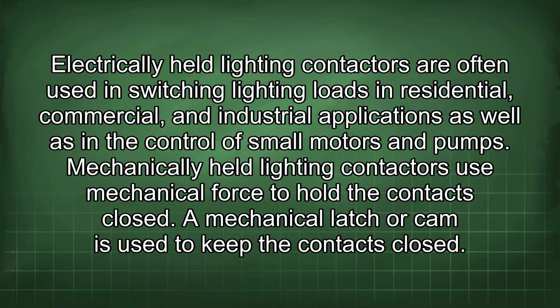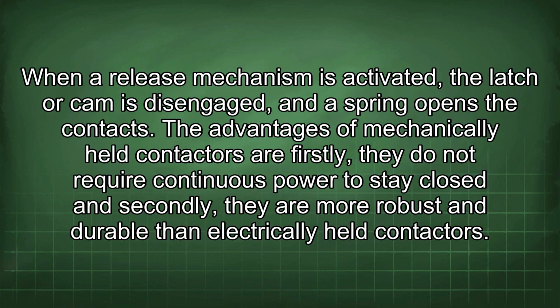Mechanically held lighting contactors use mechanical force to hold the contacts closed. A mechanical latch or cam is used to keep the contacts closed. When a release mechanism is activated, the latch or cam is disengaged, and a spring opens the contacts.